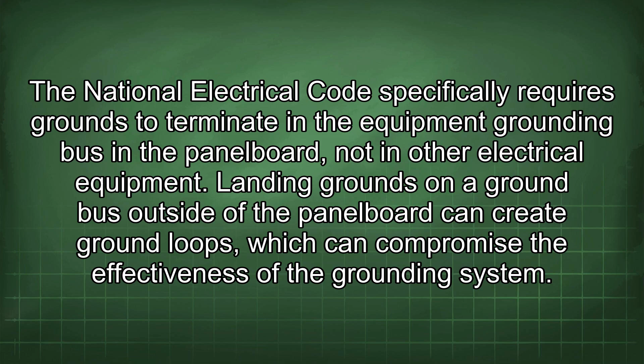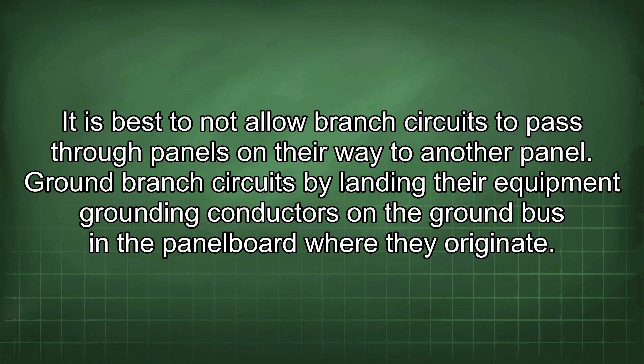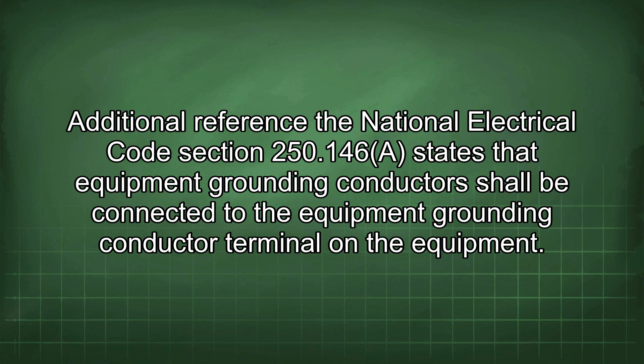It is best to not allow branch circuits to pass through panels on their way to another panel. Ground branch circuits by landing their equipment grounding conductors in the ground bus in the panel board where they originate. Additional reference: the National Electrical Code Section 250.146 states that equipment grounding conductors shall be connected to the equipment grounding conductor terminal on the equipment. Therefore, to reiterate, branch circuit grounding conductors must terminate on the equipment grounding bus bar within the panel board where the branch circuit originates, and should not pass through intermediate panels on their way to another final destination panel board.